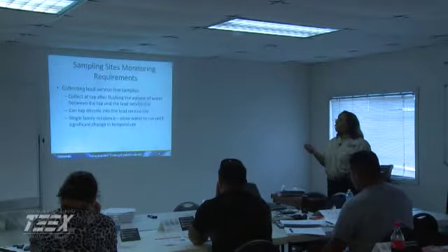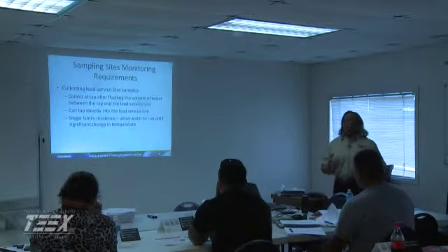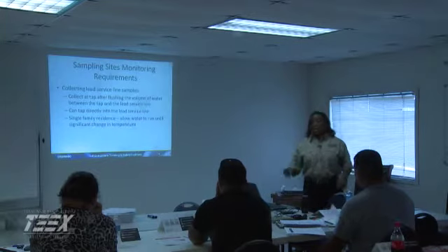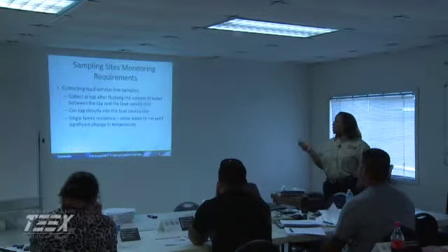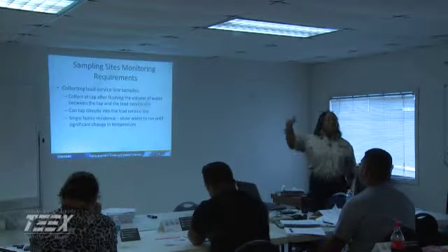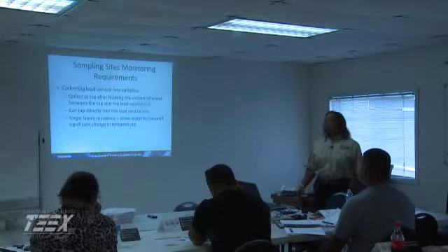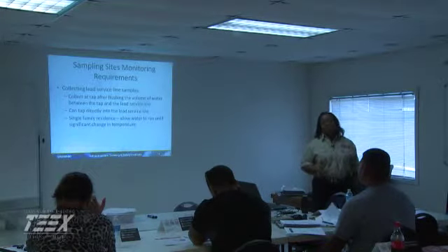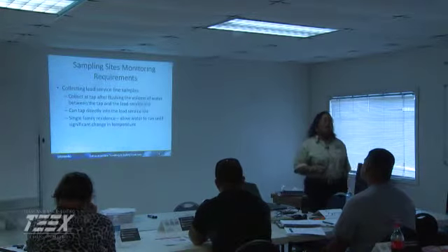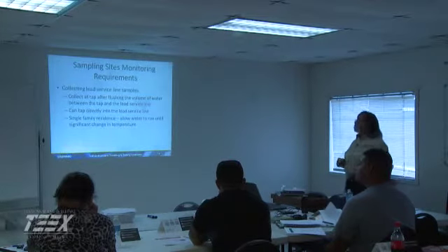You can go and tap directly into the lead service line, and that is recommended. Set up your own sampling sites. Tap into that line where you don't have to do the flushing. For single family residents, allow the water to run until there is a change in temperature. Now I know I'm getting the water from that lead service line. So for all of these, not only are you going to verbally give the instructions to your homeowners, I'd put it in writing too, so they can have something to refer back to, depending on what type of sample they're pulling.